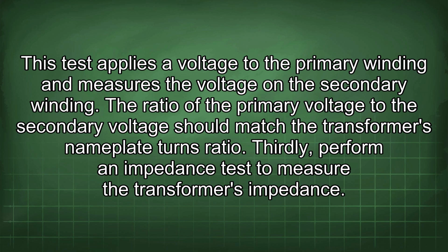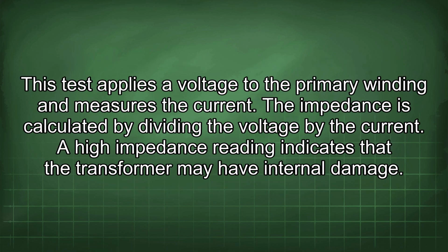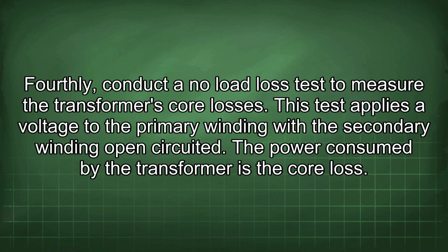Thirdly, perform an impedance test to measure the transformer's impedance. This test applies a voltage to the primary winding and measures the current. The impedance is calculated by dividing the voltage by the current. A high impedance reading indicates that the transformer may have internal damage. Fourthly, conduct a no-load loss test to measure the transformer's core losses. This test applies a voltage to the primary winding with the secondary winding open-circuited. The power consumed by the transformer is the core loss.